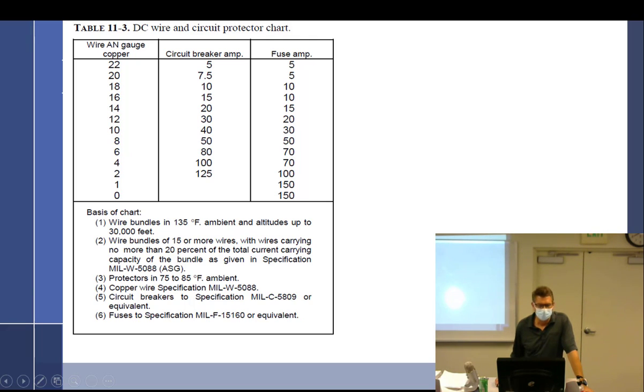So if I'm using a number 20 wire, then my circuit breaker can be 7.5 with the fuse at 5. Again, this is for wire bundles in 135 degrees ambient, altitudes up to 30,000 feet, in wire bundles, per wire specifications.